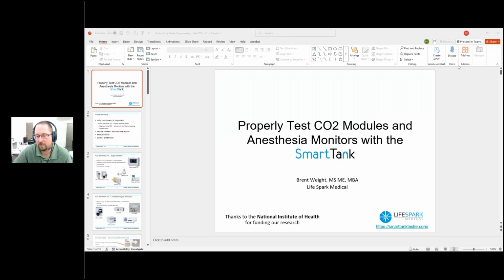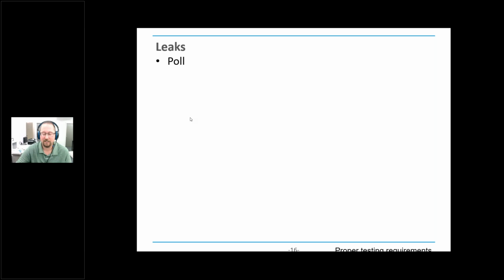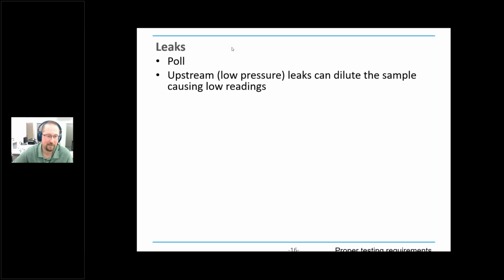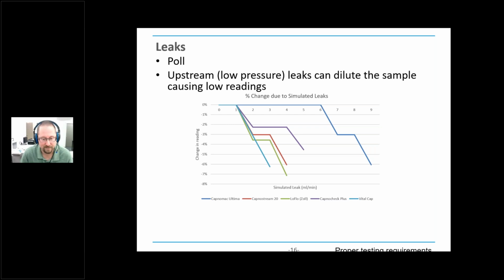I've got to get back into my presentation here. There we go. Well, that's good to hear that 75% are doing leak testing. We did not see quite that high, but that's great. So the problem with leaks is, especially if it's upstream, which is the low pressure side, upstream of the pump and the sensor, those leaks can dilute out the sample. You're essentially sucking room air in with the sample from the patient, and you're getting lower results than you should be. And so that's a problem. Here's an example. We actually did some testing, again with the NIH, to look at the effect of leaks, measured leaks on 5 different devices.